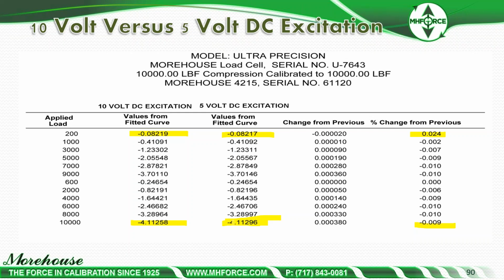So if you're going to switch voltages, you really need to have the cell recalibrated at the appropriate voltage. As part of the traceability chain, if you're applying 5 volt DC and you're switching meters, you should have traceable 5 volt DC traceability the whole way through. If you're applying 10 volt, you should maintain amplitude and waveform, all that stuff. If it's an AC measurement, you should maintain that. AC cannot be substituted for DC.